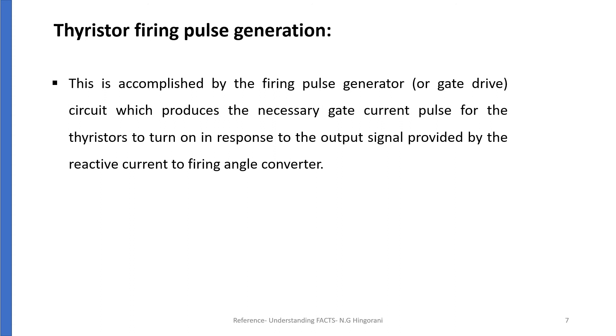The last function is thyristor firing pulse generation. This is accomplished by a firing pulse generator or gate drive circuit which produces the necessary gate current pulse for the thyristor to turn on, in response to the output signal provided by the reactive current to firing angle converter.